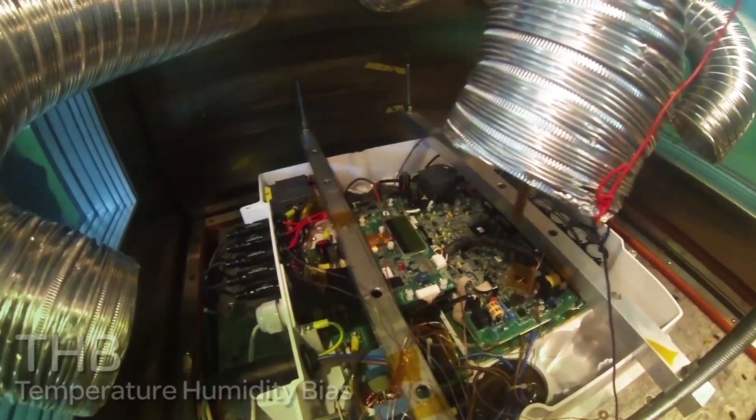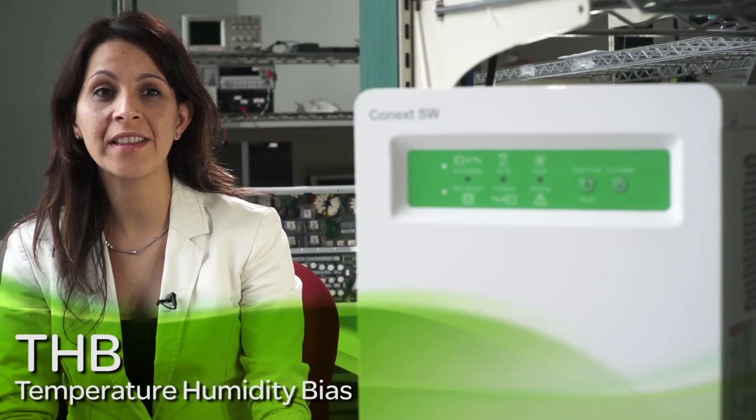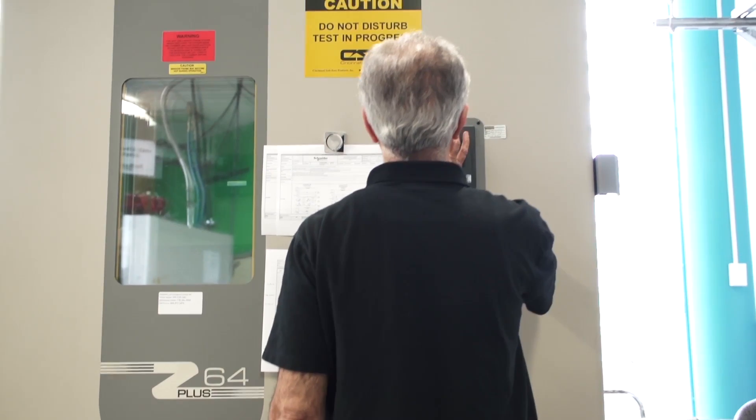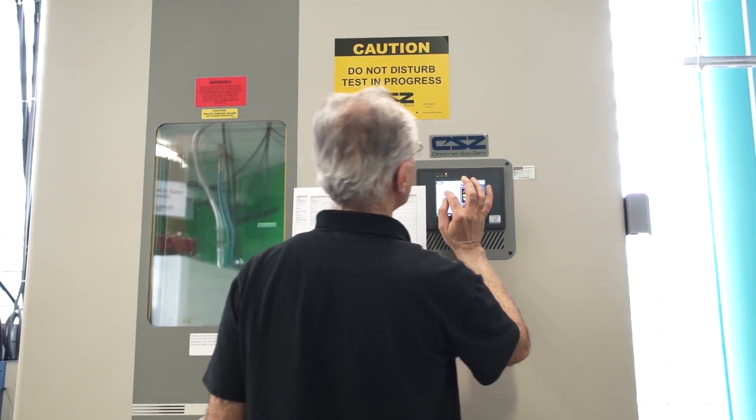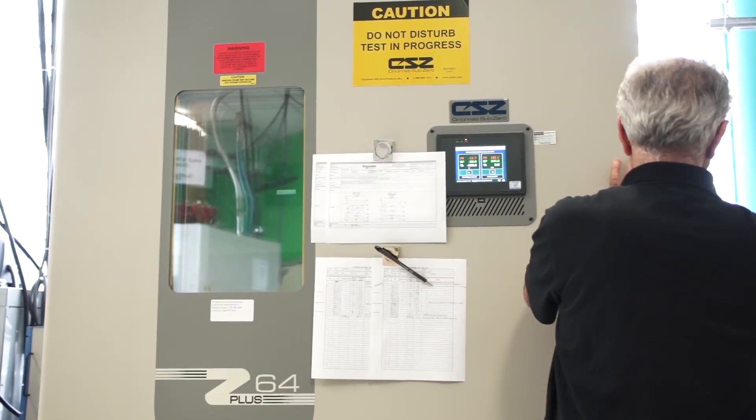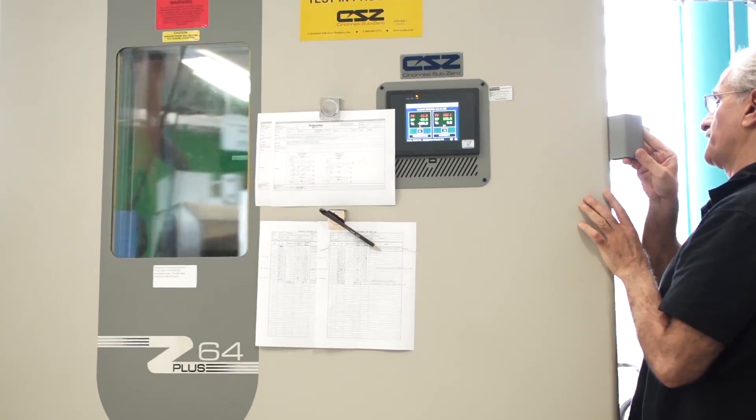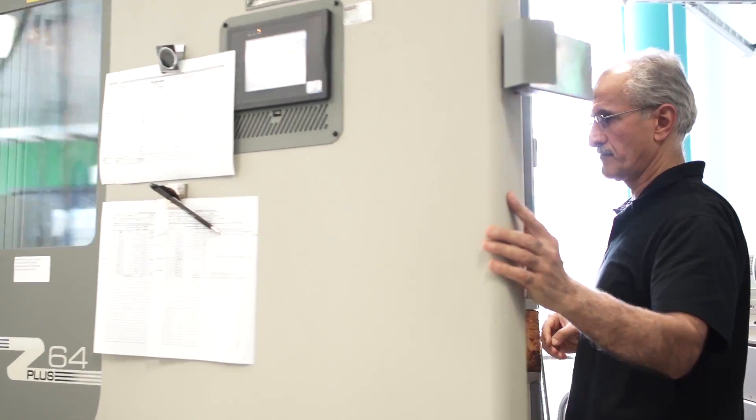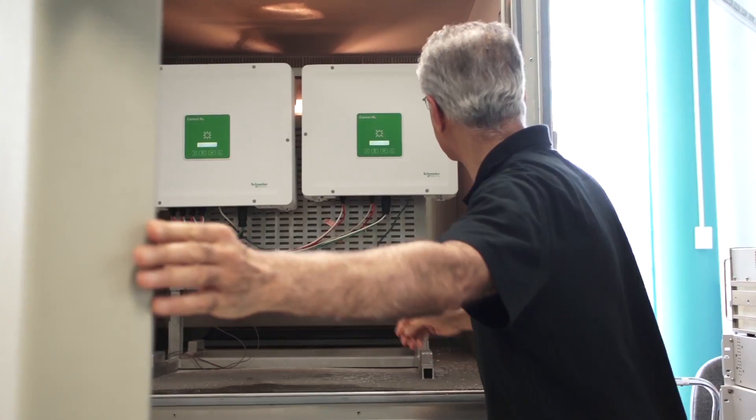Second, temperature and humidity bias testing, or THB. In this test, we accelerate the penetration of moisture inside the unit under test by keeping temperature and relative humidity at high levels for a long period of time. This is to understand how the product performs in hot and humid conditions and determine its robustness against humidity, electro-migration, rust, or corrosion.